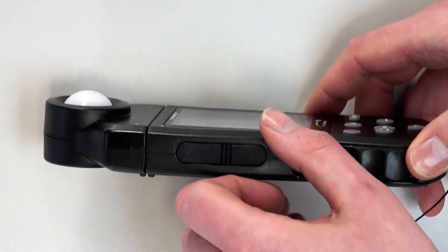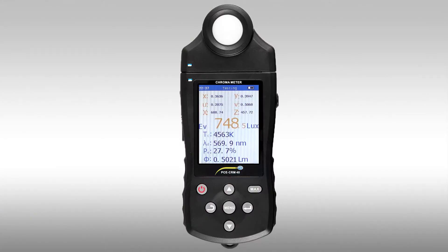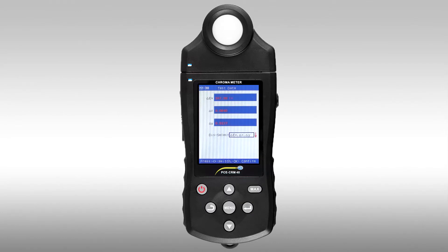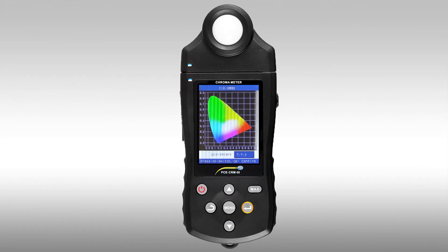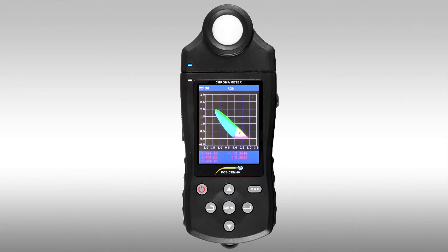On the side of the PCE-CRM40 you can find the micro USB interface to access the memory. Using the middle menu key, we come into the main menu of the PCE-CRM40. Here is a test function which is activated with the enter key. Here we can see the color difference of the actual measured value, we can see the color spectrum, and the color spectrum in RGB form.